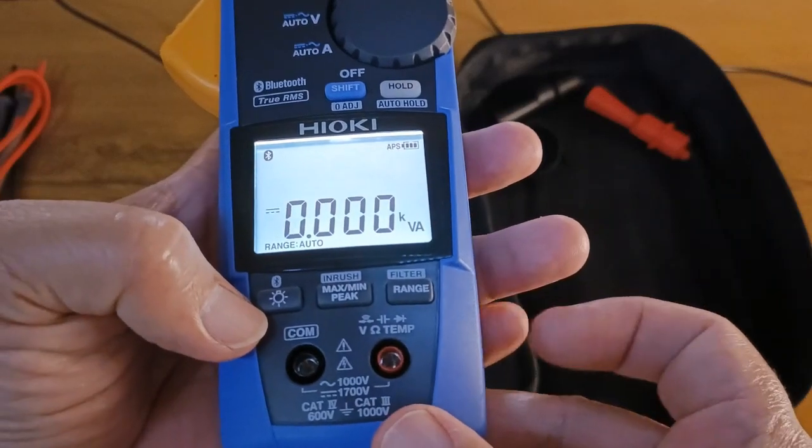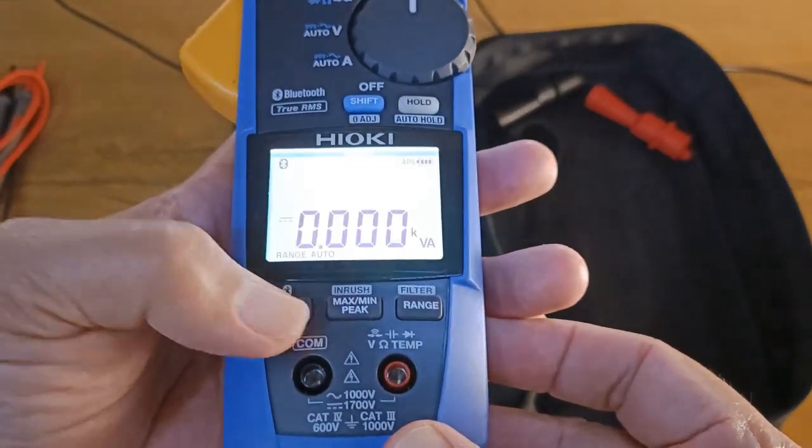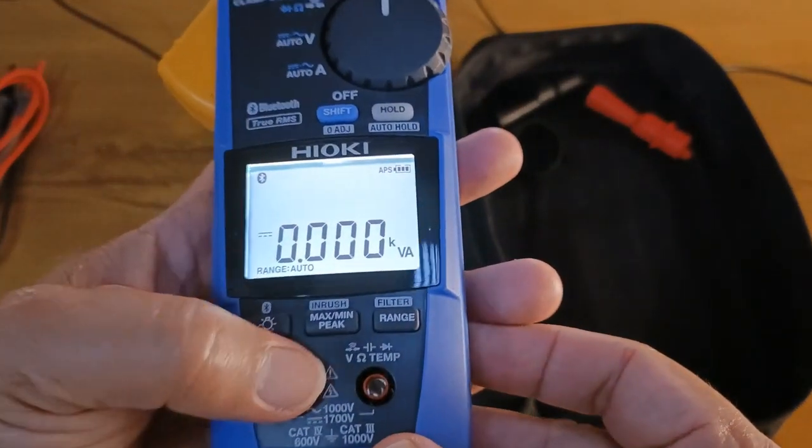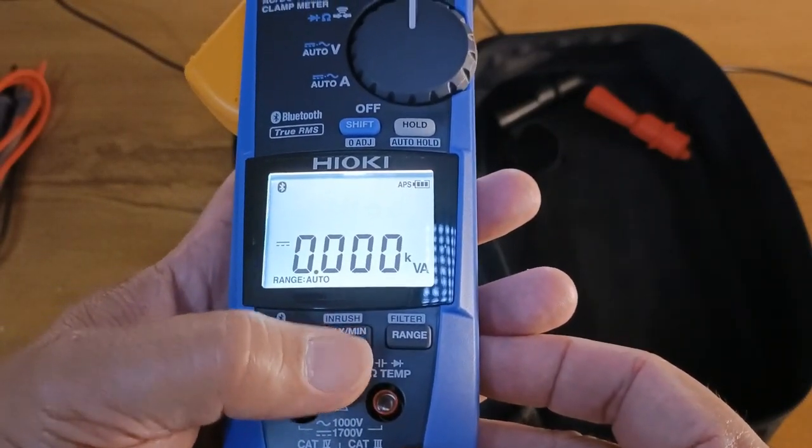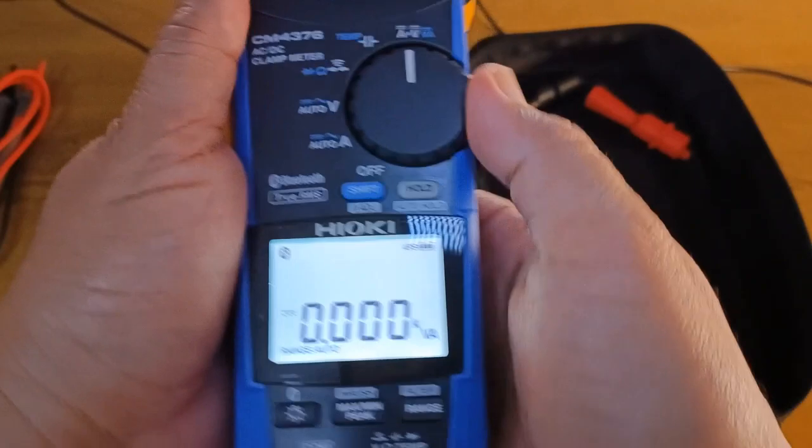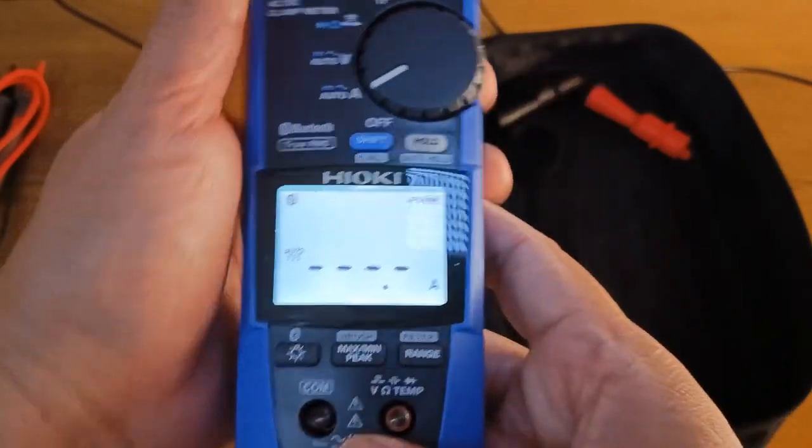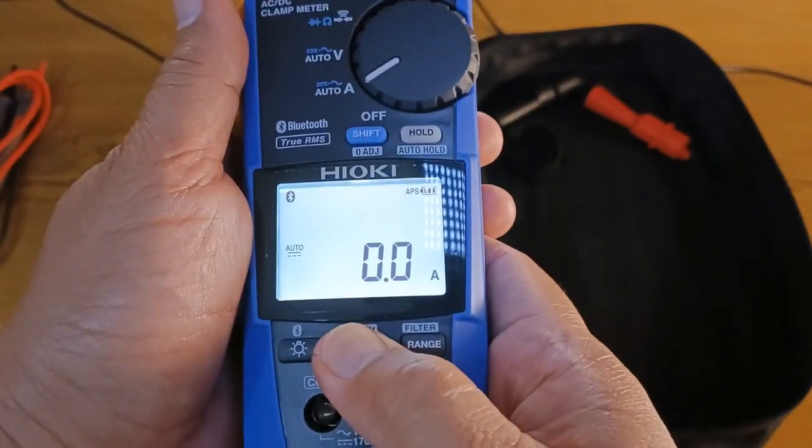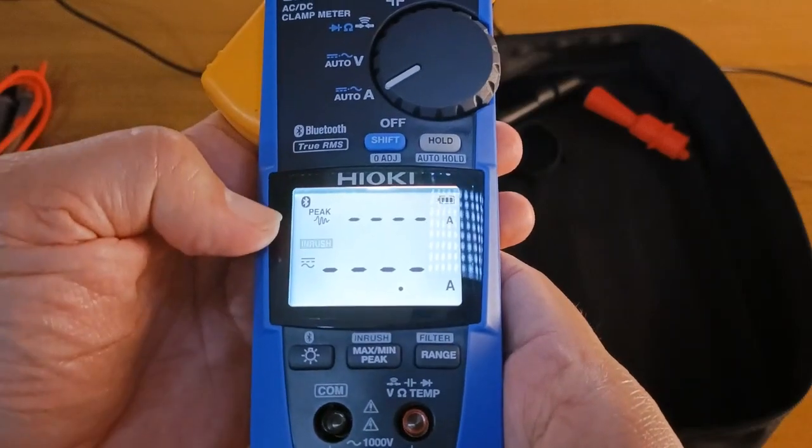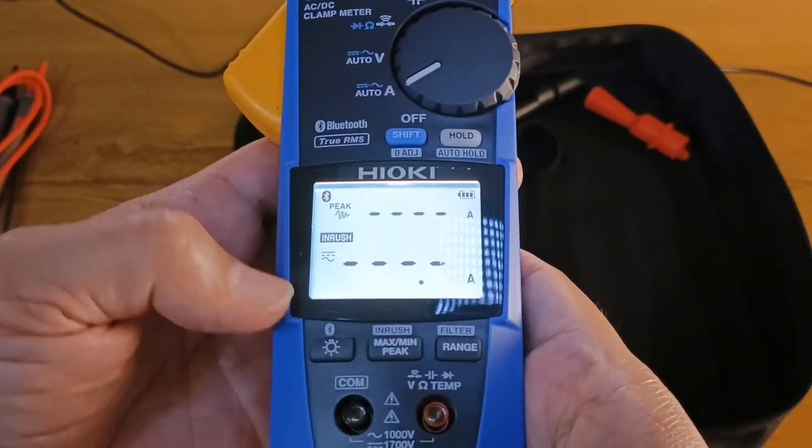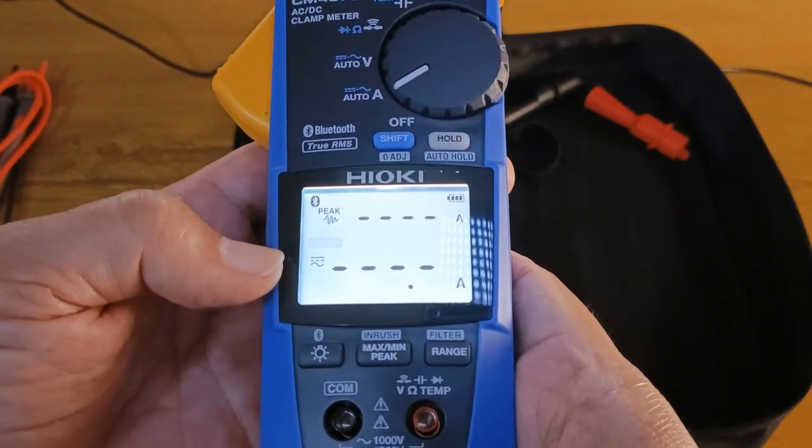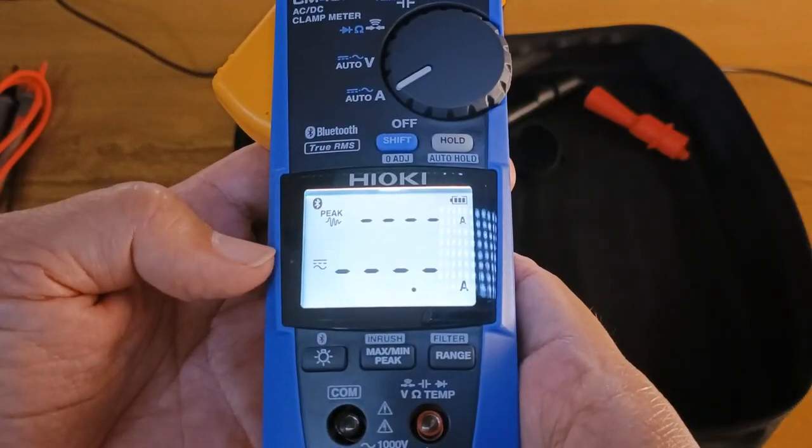The screen of the CM4376 has a very uniform backlighting. It has buttons also for mean, maximum and peak values, including inrush current. Now the inrush current has two displays: it can display the instantaneous peak value of the waveform and the RMS value of the inrush current, so you have two values that you can use.